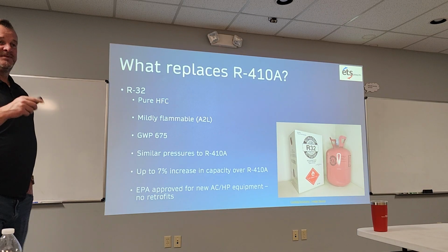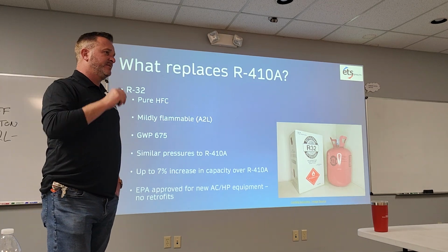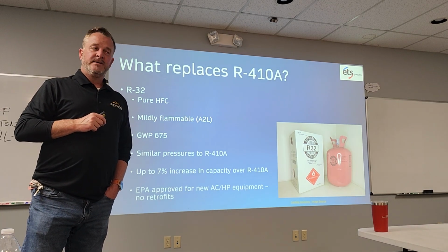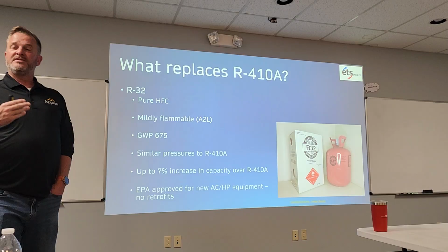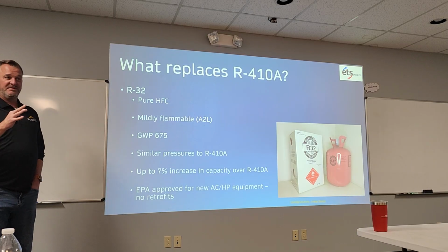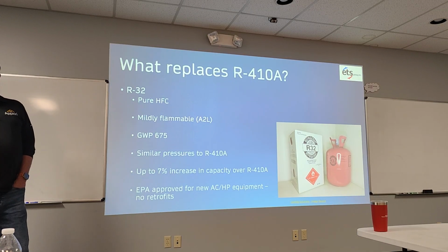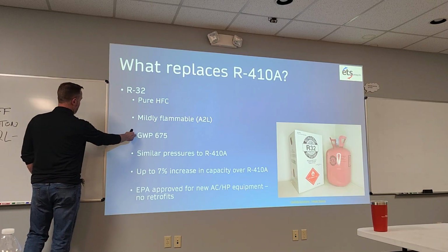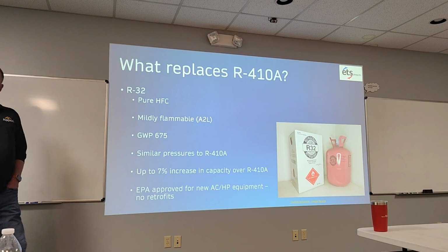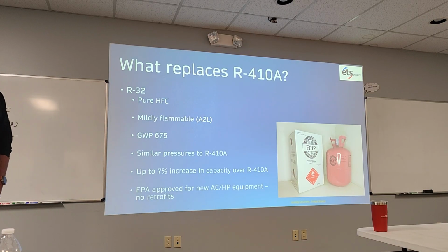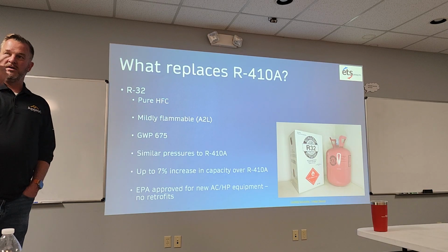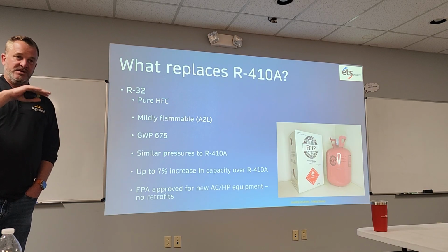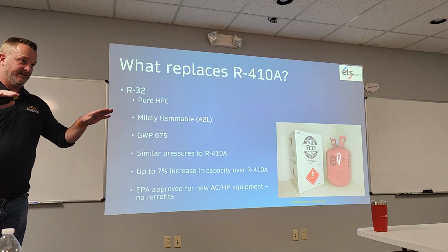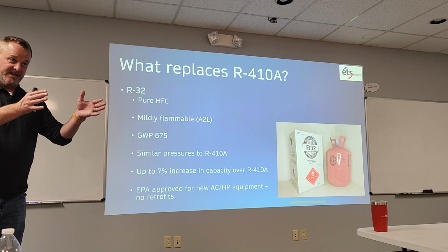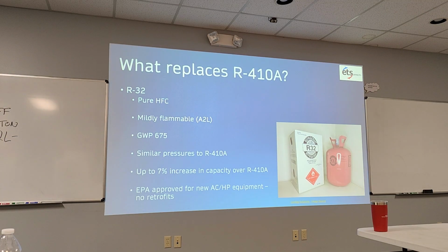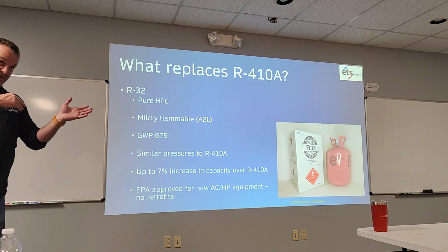The other thing I wanted to bring up, have any of you seen the flex coils people talk about out there? There's a certain brand, I won't name it, that calls it a flex coil. There's a lot of misinformation around this. The same sources that told me about the 600 number also told me about this flex coil. What they were saying is you can use this flex coil in a 410A or an A2L system. There's no such thing as that. I just want to make that clear.